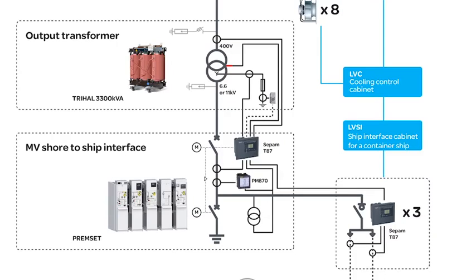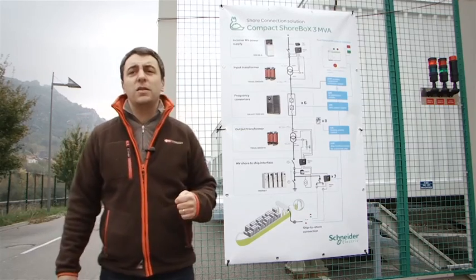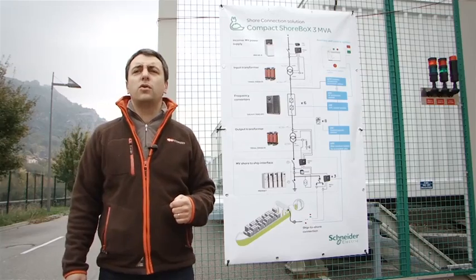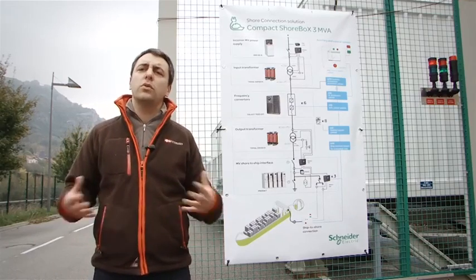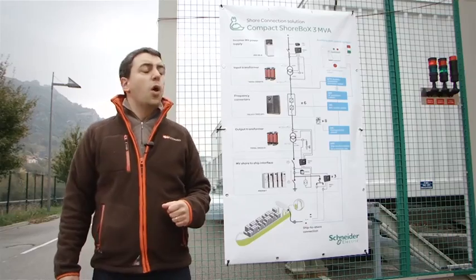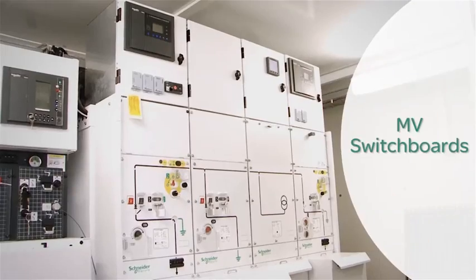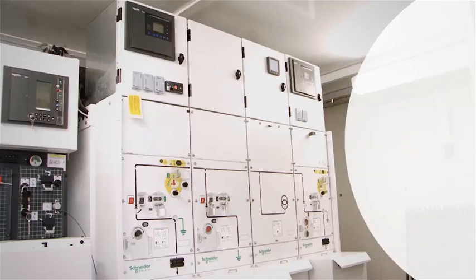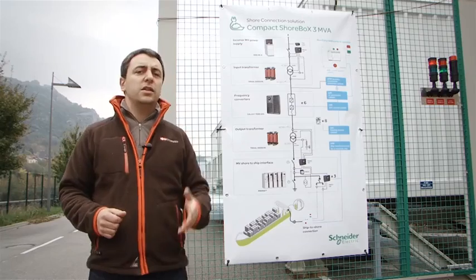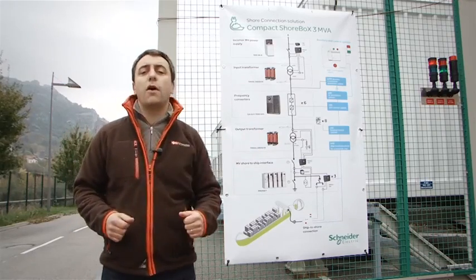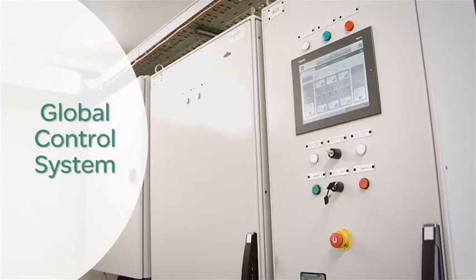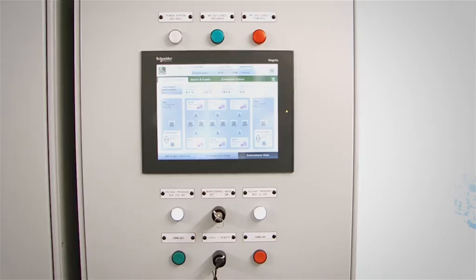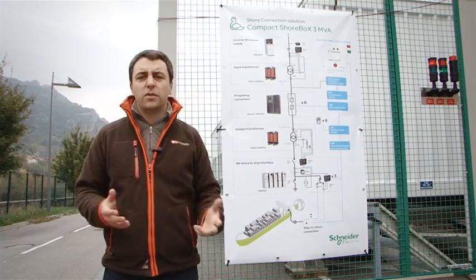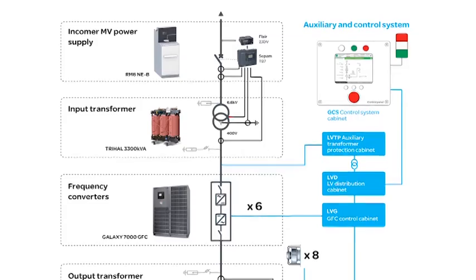Downstream, we will find the last MV switchboard with several functions. The first function is the main circuit breaker. We will also have a grounding switch whose role is to automatically ground the system during the connection. We will also find up to 3 connection points, with each of them being equipped with a dedicated switch. In addition to these 5 stages, we will find a set of auxiliary cabinets and switchboards managing different functions: global control system, HMI, low voltage distribution, cooling management, frequency conversion interface management, as well as ship interface management.